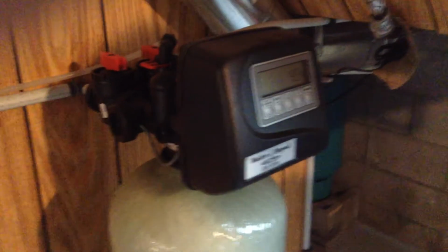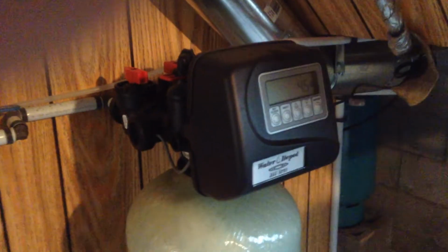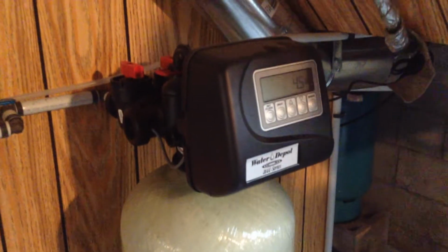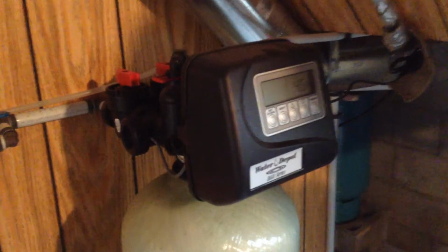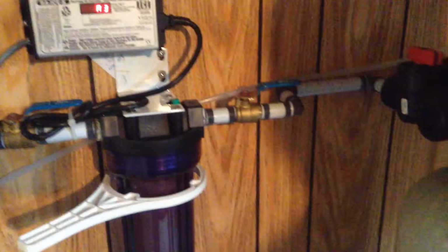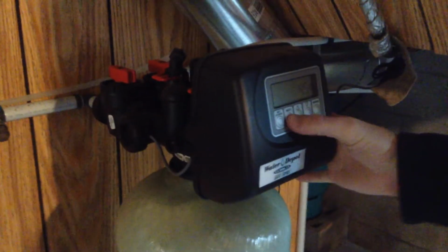You have a 1/2-inch copper line coming from your pressure tank. A 1/2-inch line is only going to service a certain amount. The way to increase that flow rate, if the pump can handle it, is to go to a bigger line, like a 3/4 line like this. You might be able to get 6-7 gallons per minute.